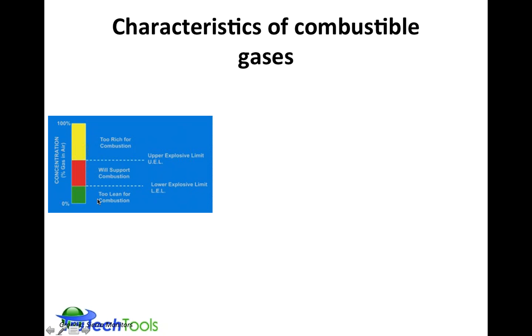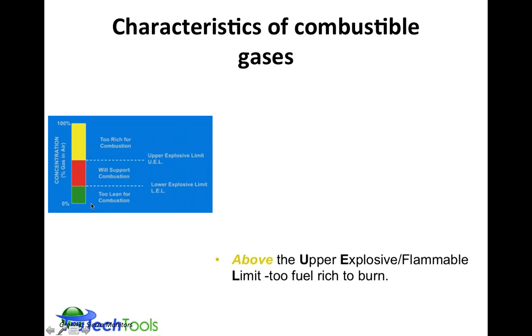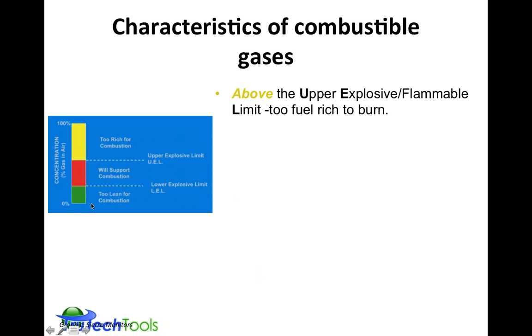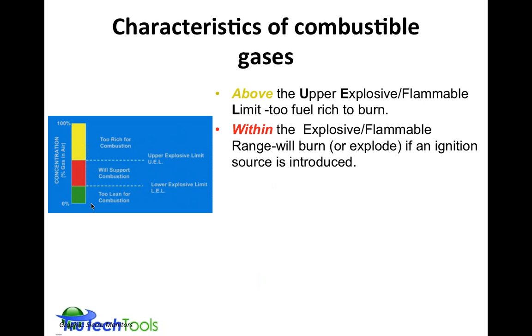So the goal is always to stay below the lower explosive limit, and in fact, most standards are written, as the BPI 1200 is, to have it at 10%, or a very, very low level. And that's because situations can change very rapidly. So above the upper explosive limit, it's too fuel rich to burn, the yellow zone, but that doesn't mean it's safe. That's a caution area.